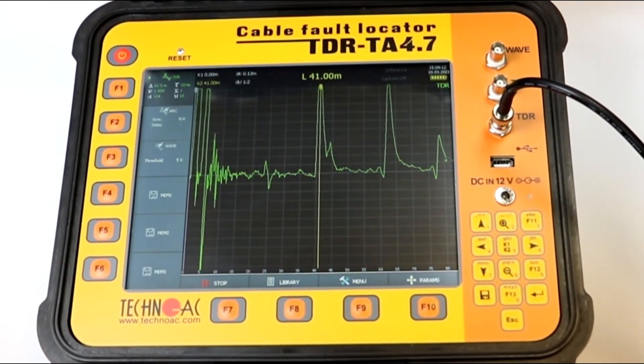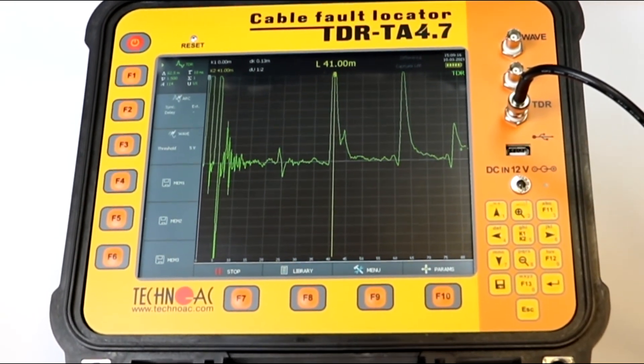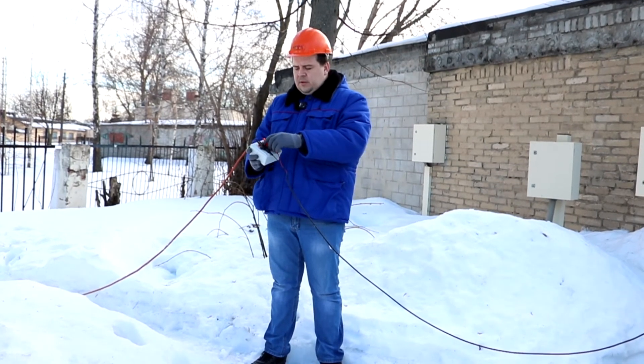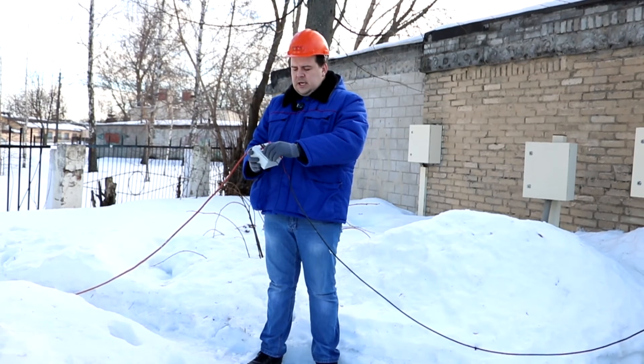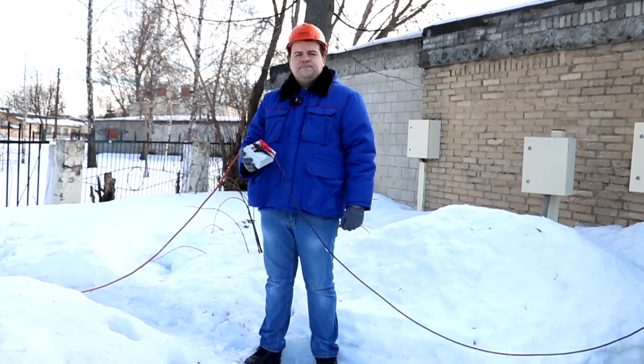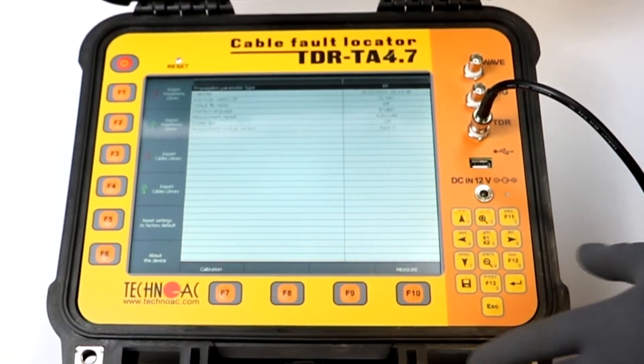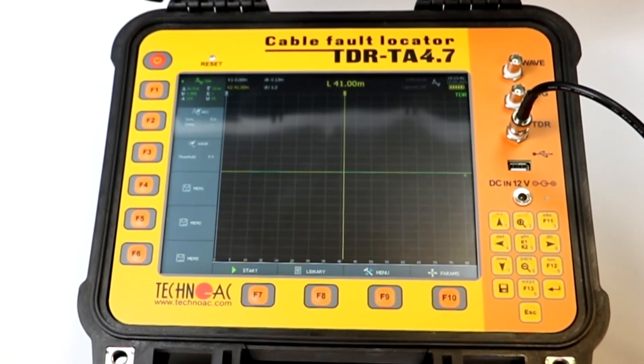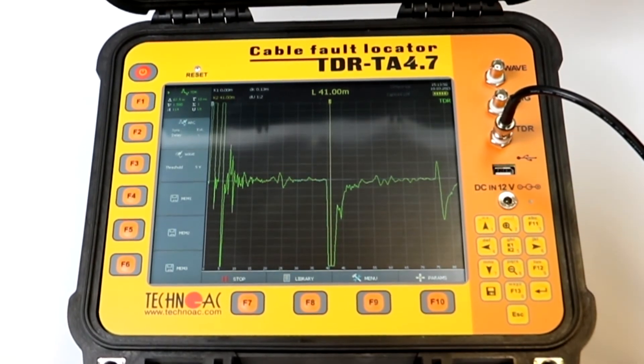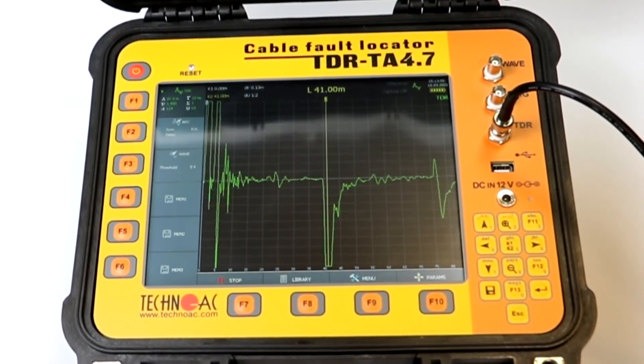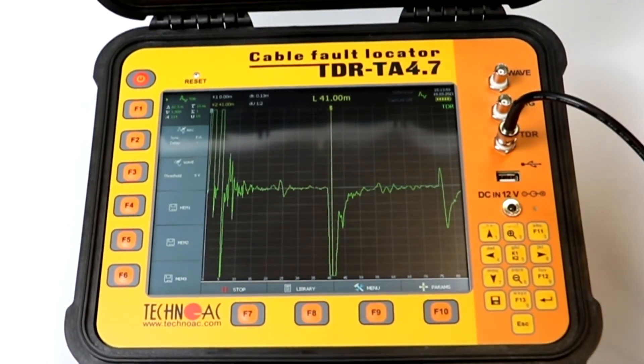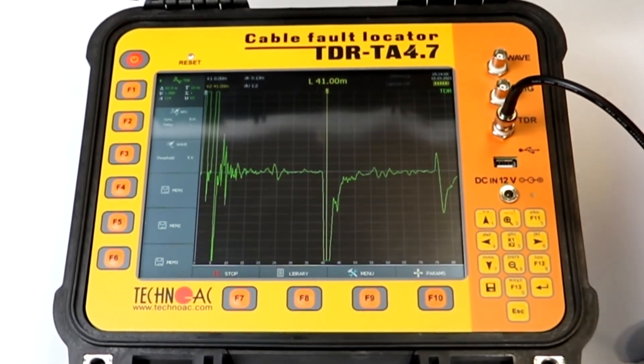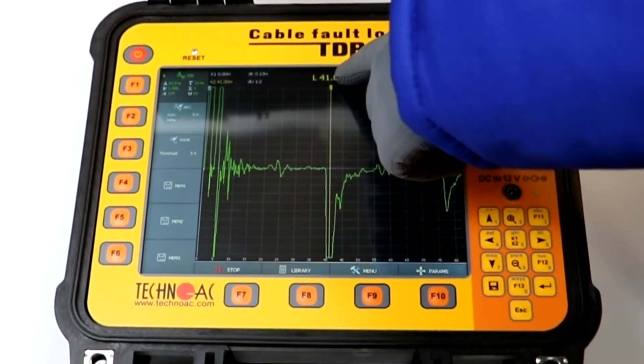Let us reconnect the cable so we can see what other damage this device can find. We will reconnect the crocodile clamps to the other two conductors — the red one to the gray conductor and the black one to the brown conductor. After entering the main menu, we press F10 again, then start the measurement by pressing F7. As you can see in this case, the graph is going down, which means there is a short circuit between two conductors of the cable — also at 41 meters.